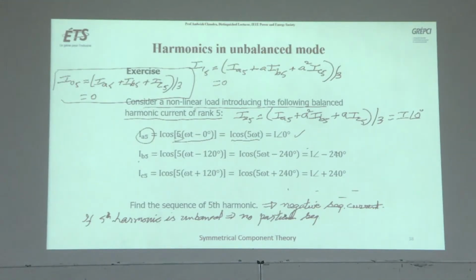Now for the fifth harmonic, this is for phase A; for phase B it is minus 120. The fifth harmonic is there. Why is it minus 240? Because 5 you can write as 3 plus 2, multiplied by 120 degrees. So 3 multiplied by 120 is 360 degrees, which is 0 degrees. It remains only 2 multiplied by 120, so it will give you minus 240. Similarly here, 5 multiplied by 120 gives finally plus 240 degrees. So you put these values here.